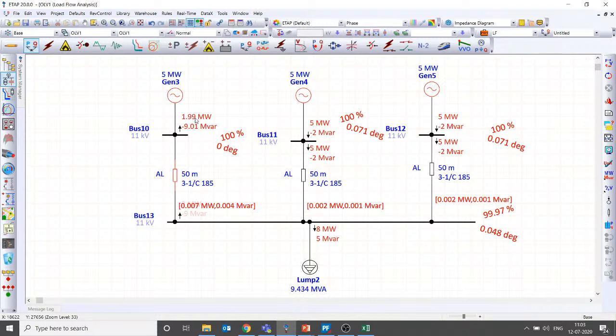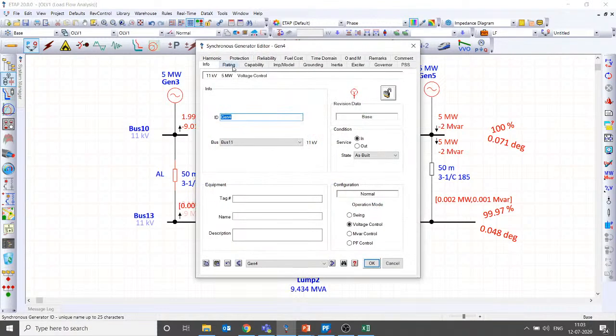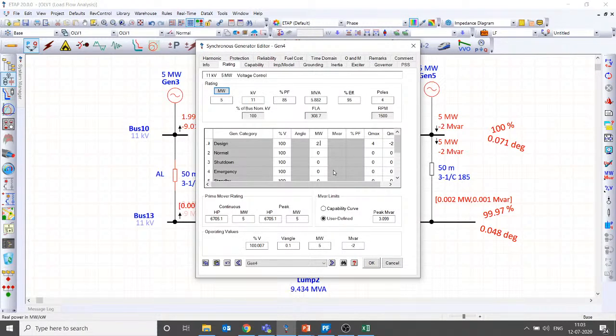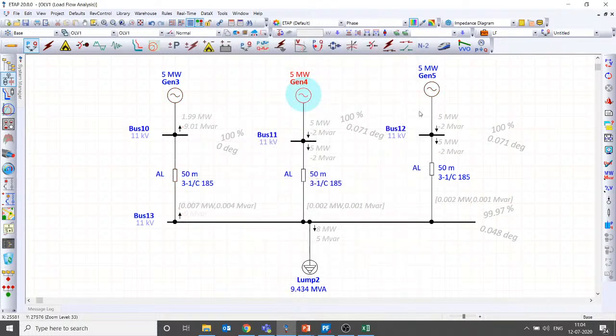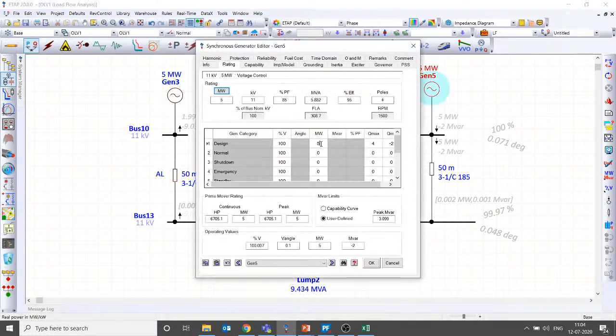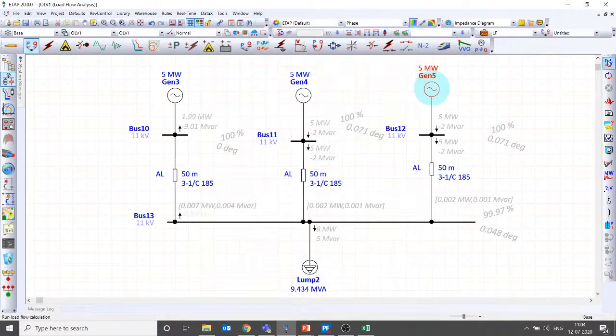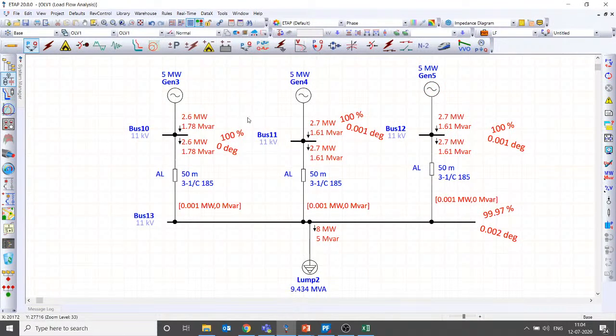So whenever there is a demand change, you have to divide this 8 and feed it here, like 2.7, 2.7, and adjust the data manually. Then the results will be right, but you need to do that exercise manually for each and every load change. Then your results will be approximately okay. Still there is a small mismatch because the load is 8 megawatt and I have not exactly divided 8 by 3. You need to understand the load and divide it equally among all the generators. And this becomes much more complicated when the generators are at different capacities.